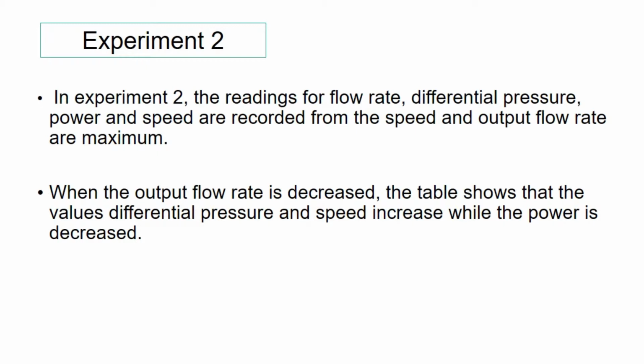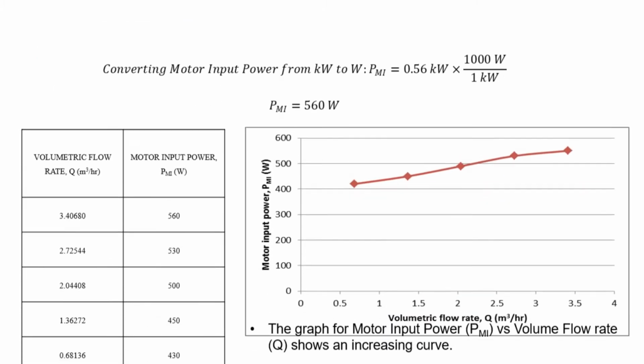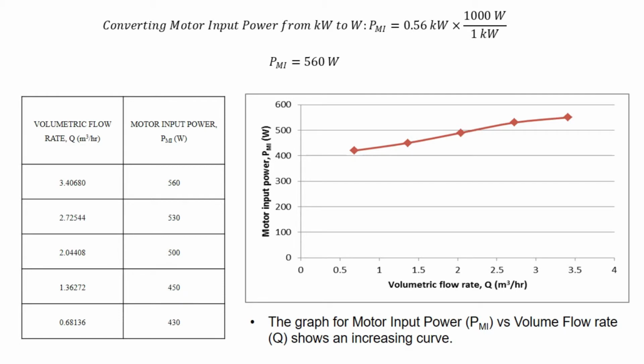In experiment 2, the readings for flow rate, differential pressure, power and speed are recorded from the speed and output flow rate are maximum. When the output flow rate decreases, the table shows that the values of differential pressure and speed increase while the power is decreased. For analysis in experiment 2, we convert the motor input power from kilowatt to watt by using the equation. From the table, we can see as the volumetric flow rate decreases, the motor input power also decreases.